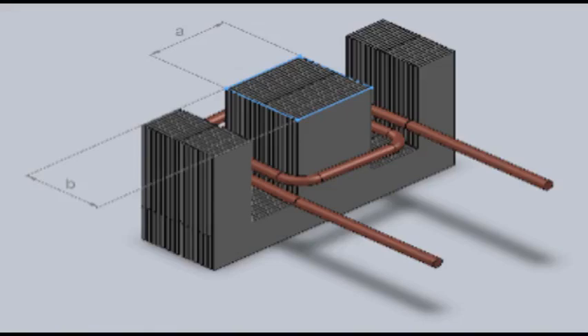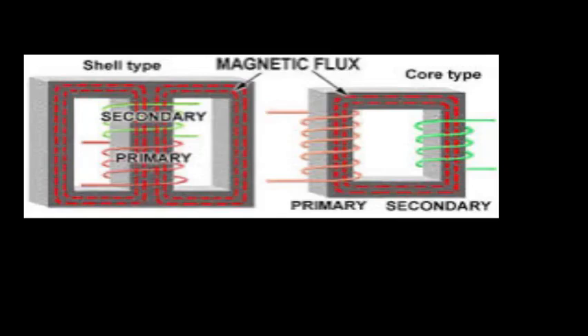So section 3, core area and why it matters. We will now look at the core cross-sectional area, since it obviously contributes to the overall dimensions of the transformer. Magnetic flux phi flows through the core's cross-sectional area A, given a flux density B, measured in Tesla. See the later section explaining what 1 Tesla is. Feel free to jump around using the timecodes. So B is phi over A, and to avoid core saturation, we must keep B under circa 1.5 Tesla for silicon steel.